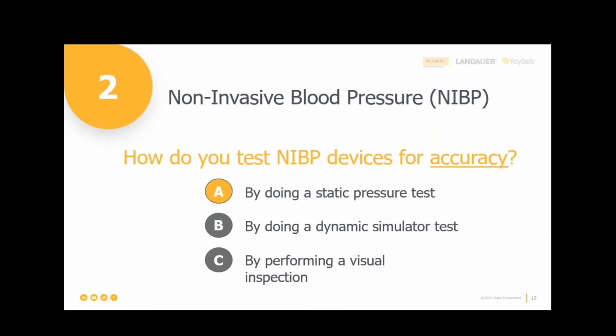All right, so we do a leak test, pressure relief test, and now we're ready to do a series of static pressure level tests. And so we want to test through the whole range. How many test points is up to the manufacturer and the manufacturer's brand and model specific test procedure. If we have to write our own test procedure, we want enough static pressure level test points to make sure that we have linearity across the range of the measurement. And then, after we do that, we'll do the dynamic simulation, assess the repeatability, and everything should be a lot closer and more within our expectation about what we see displayed on the monitor.